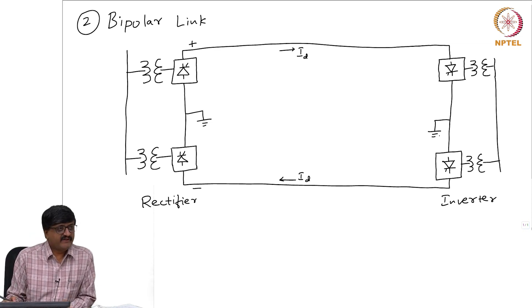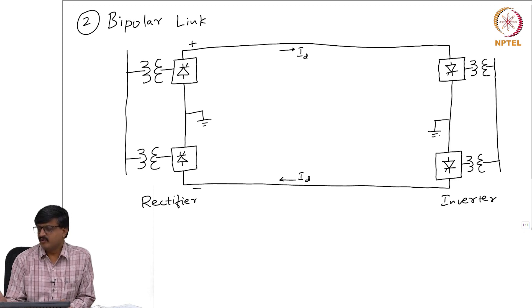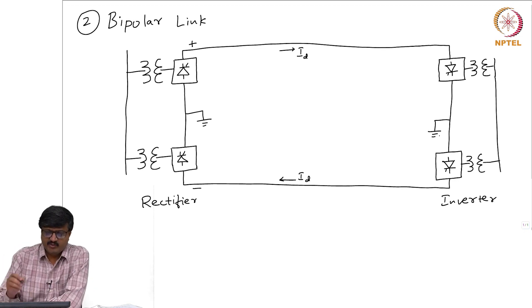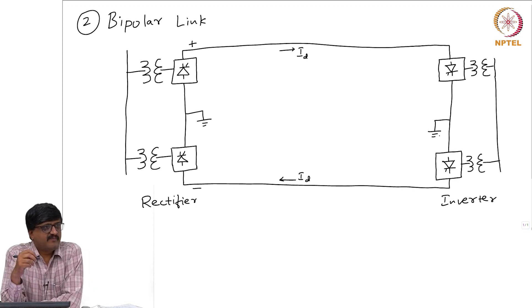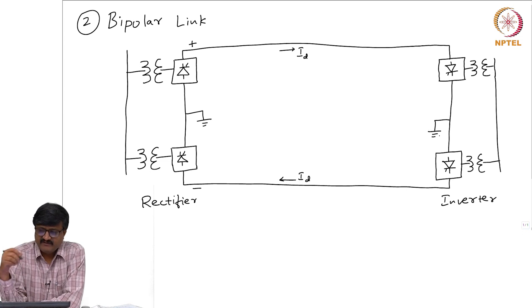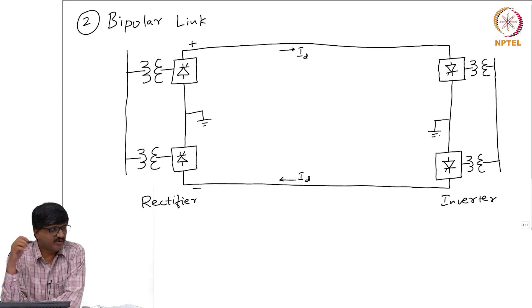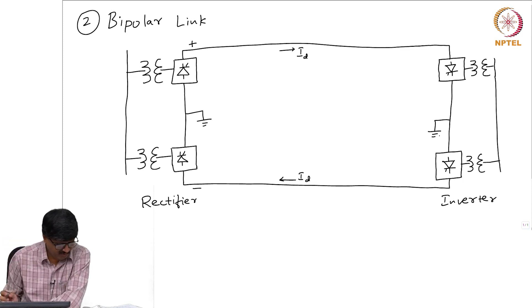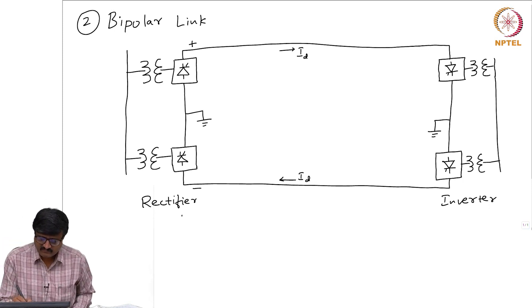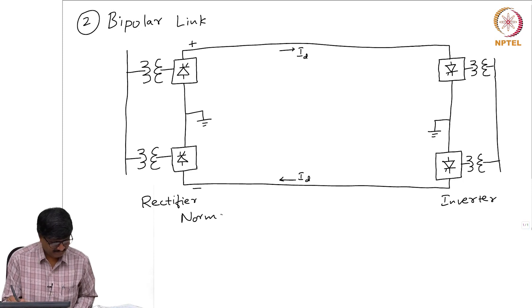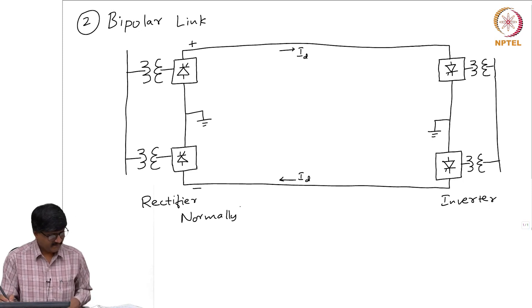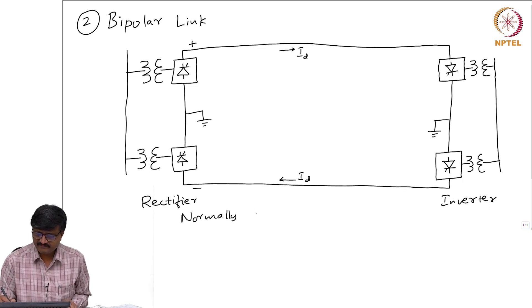The purpose of grounding on both sides does not mean that current will flow through the ground, though there is a closed path. The two 12-pulse converters are operated identically so that the current I_d is flowing only through the two conductors and there is no current through the ground. Normally, ground current is zero.